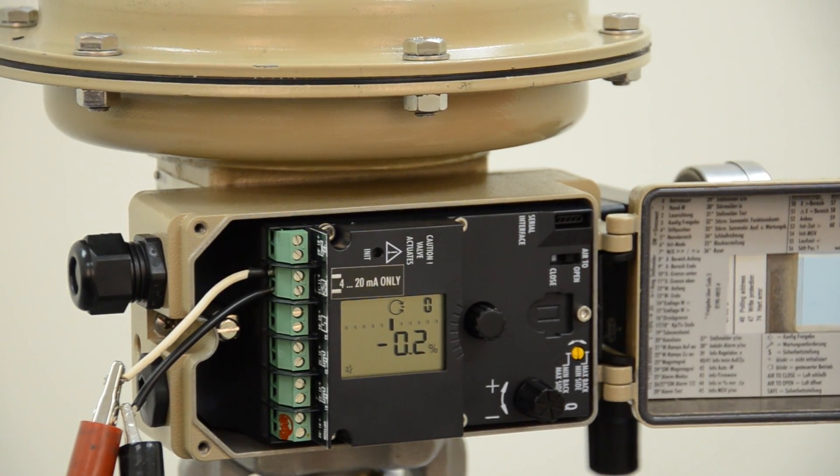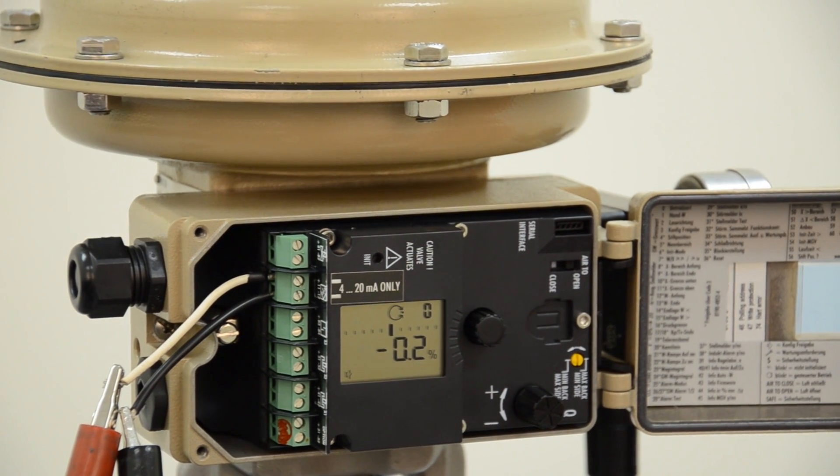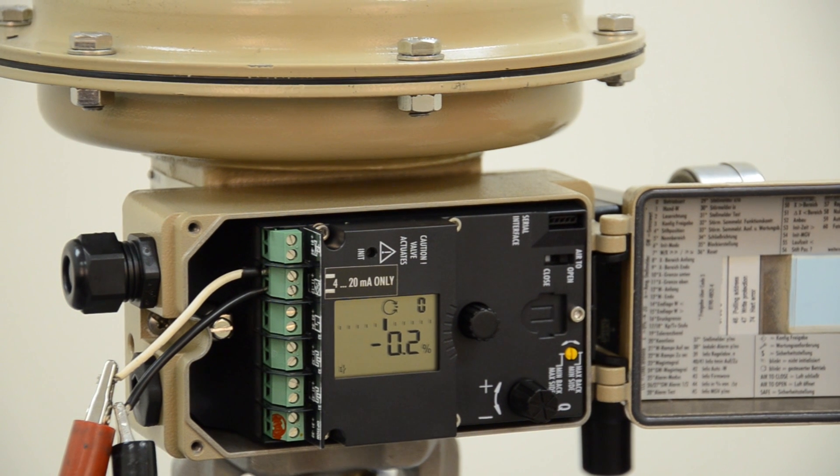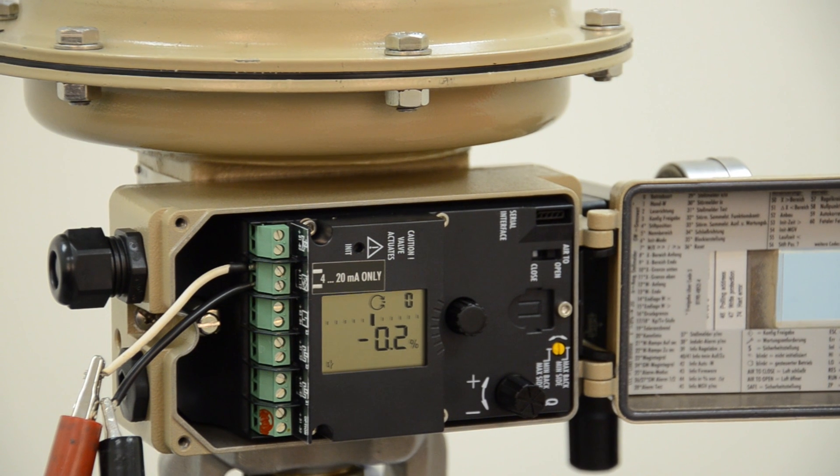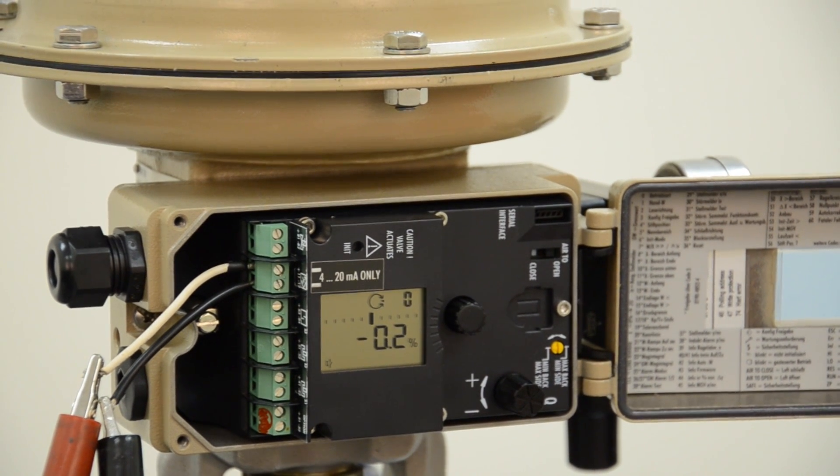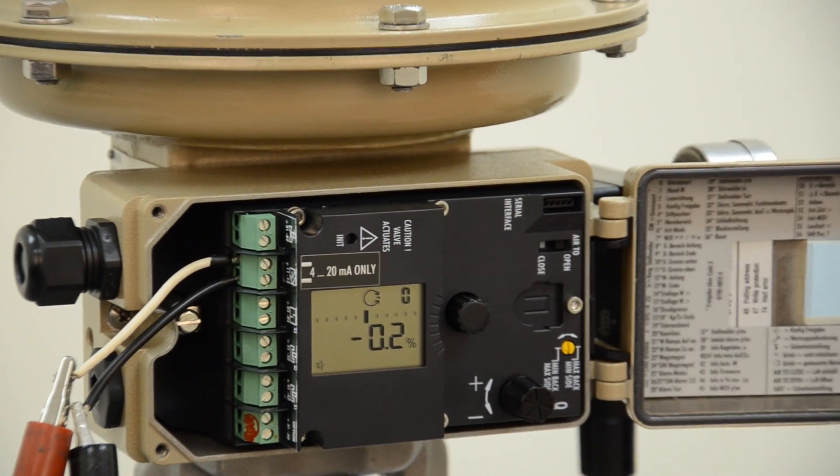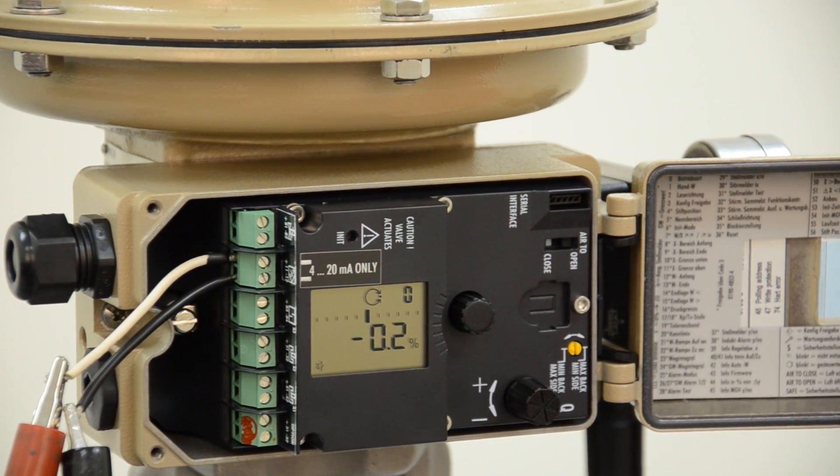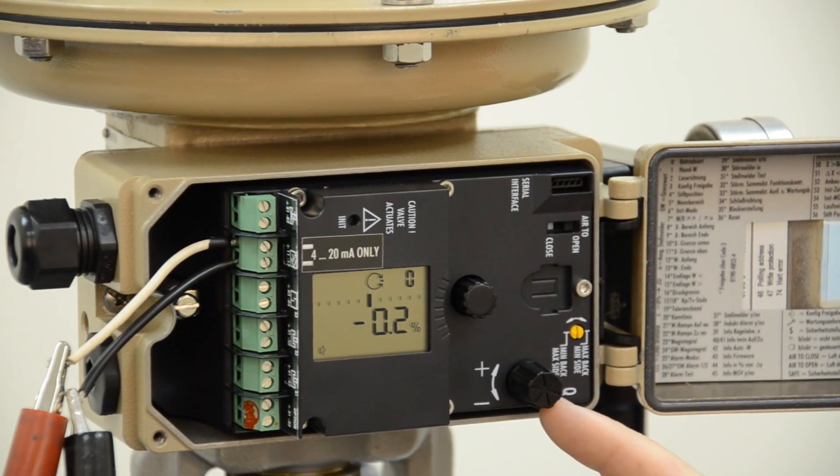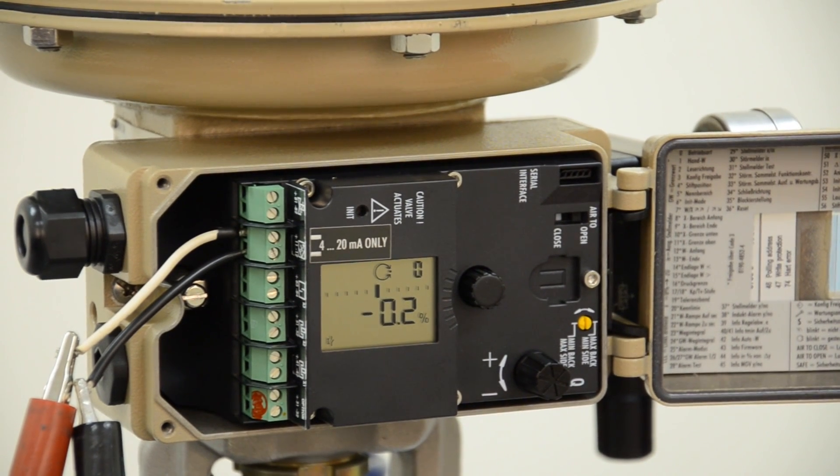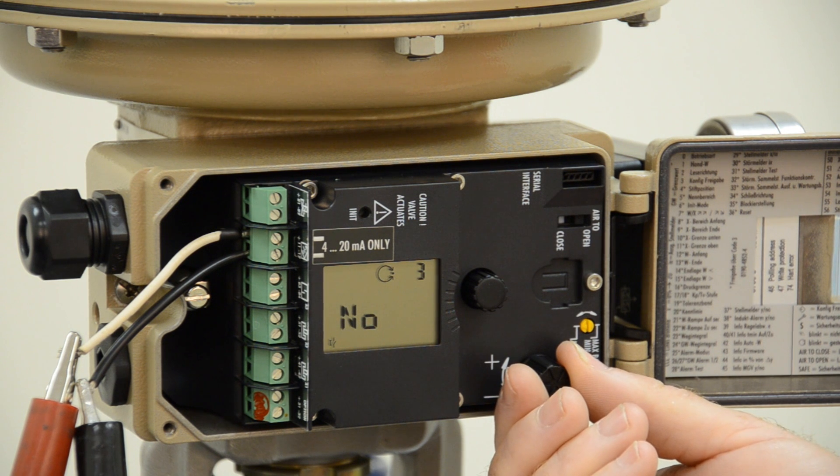Okay, now that the positioner has gone through its self-test and everything seems to be working properly, we can now start the configuration for the control valve that we're working with. In the upper right-hand corner of the display, you'll see a code number. Right now, it is on zero. To change this, we use this rotary push button. The first code we should go to is code number three.